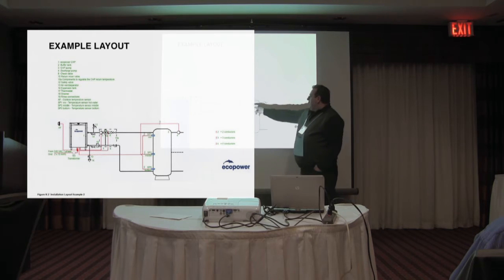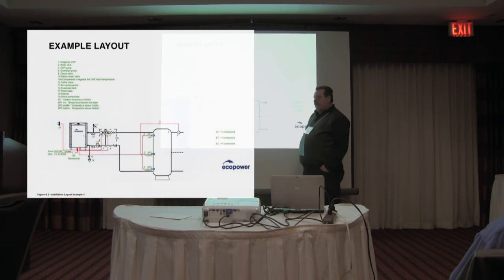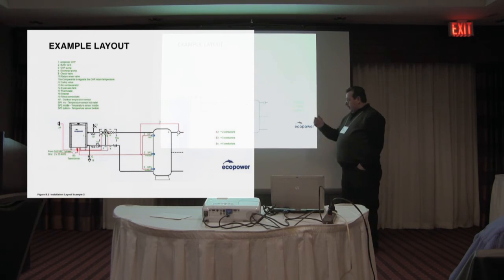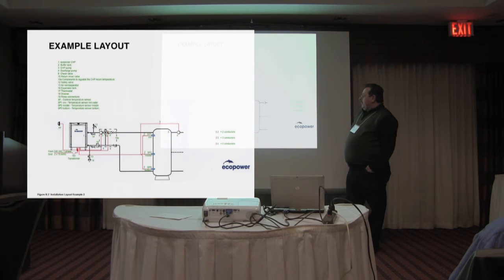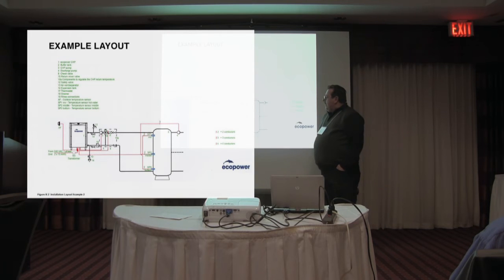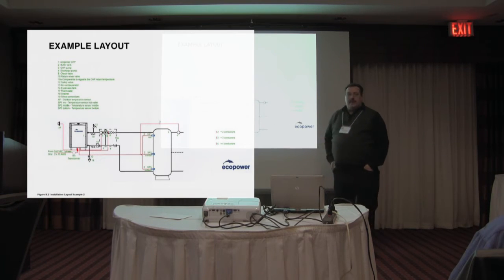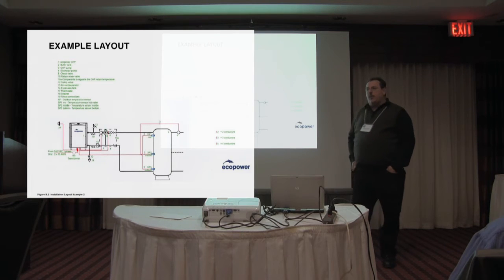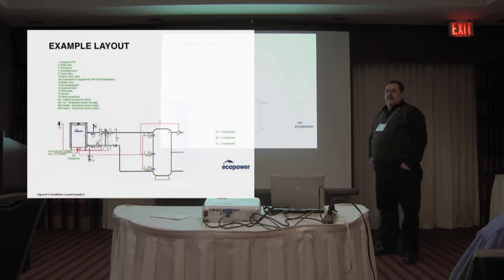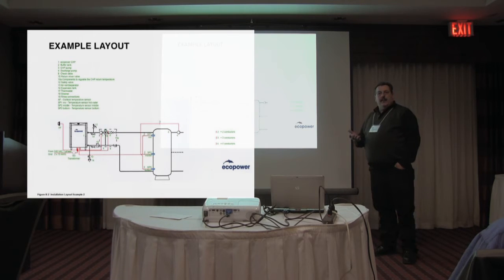And you can see all this is between the unit and this tank. This is a 250-gallon storage tank, insulated of course. Small circulator, and that's 1-inch copper pipe between the two. And then there's a mixing valve there. The only purpose for that mixing valve is that when that engine starts, if you're going to start with cold water temperature, it's to bypass some of the water to get that engine up to temperature fairly rapidly. And then the valve will start to open up and start exchanging water to that tank.